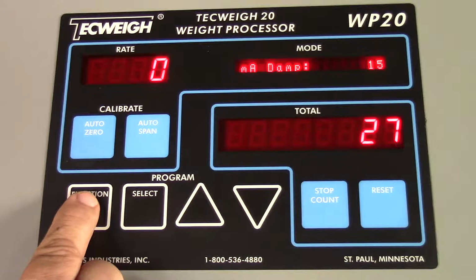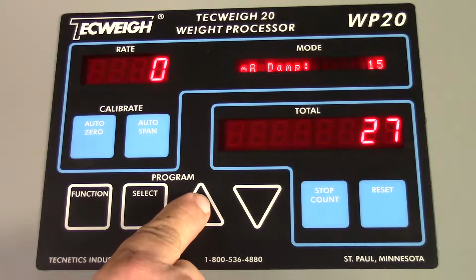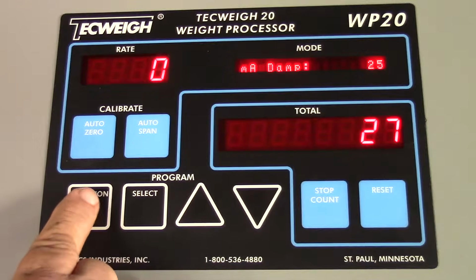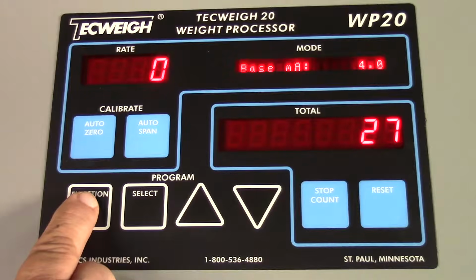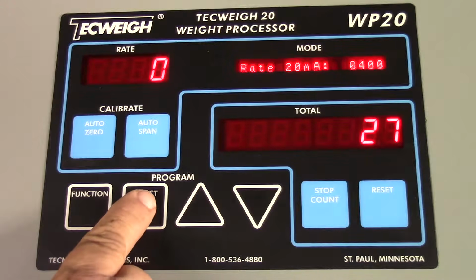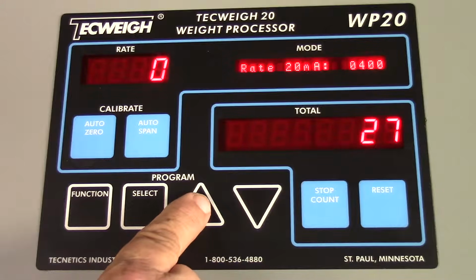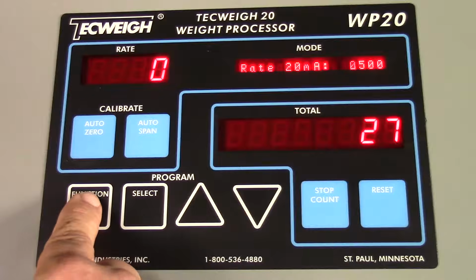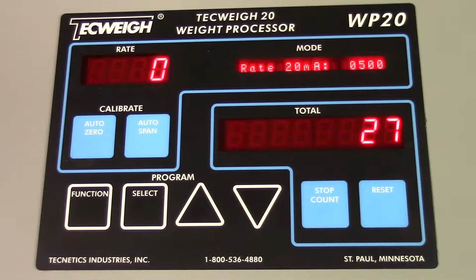Move up to milliamp damping. If we want to change that to any particular value, we can. I may increase it up to 25. This is where we could set our 4 milliamp value. Generally, we'd leave the base milliamps at 4. This is for setting up the 4 to 20 milliamp output. And for the most part, here under 20 milliamps, we'd put the max tons per hour.